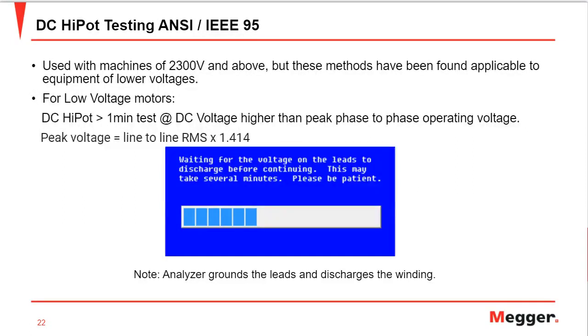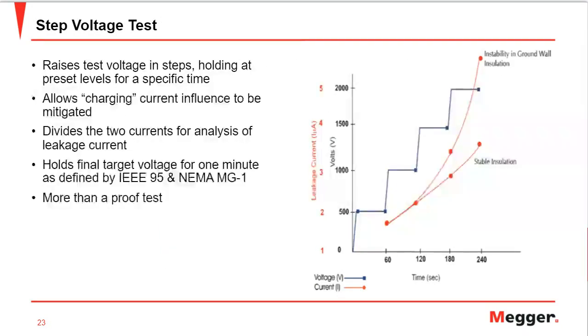We'll start with the step voltage test and see more into it, and of course after the step voltage test, we'll see the ramp voltage test. So as we discussed, it raises the voltage in steps and then holds the voltage for a minute, then calculates the leakage current, and then it goes to the next step, holds for a minute, calculates the current, and does the same process 5 times.